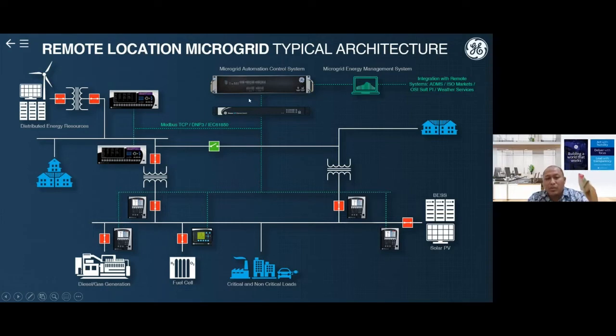And then from the microgrid controller, it can be monitored through an HMI we call the energy management system. As already mentioned before, inside the microgrid it's not only the controller, but it also consists of the power sources, such as here on the top left, the distributed energy resources. It can consist of wind turbine, solar PV, and also battery storage. And as a backup, the customer can also use diesel or gas generation or fuel cell.